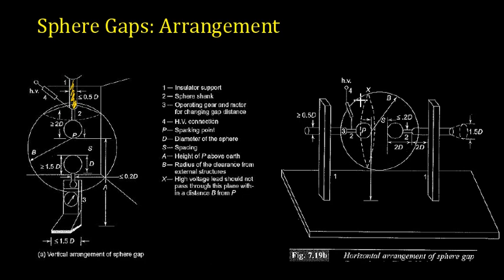In both the cases, here you can see that your X is here. So your high voltage lead has to be away from this X. Your high voltage lead is provided at this point because you have a sparking point at P. So at P you will get a spark point. You have to keep your high voltage terminals away from P, and so we are making sure that you are having a uniform distribution of field around this sphere.